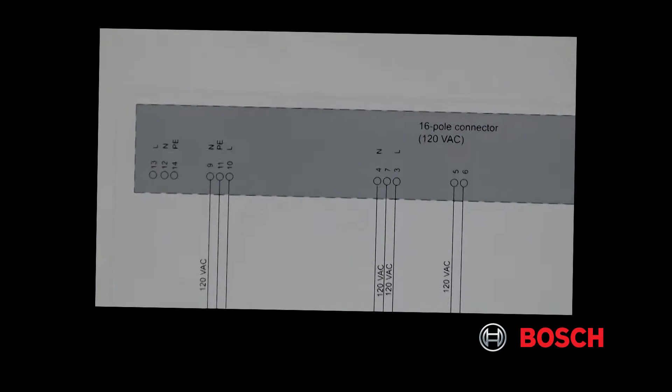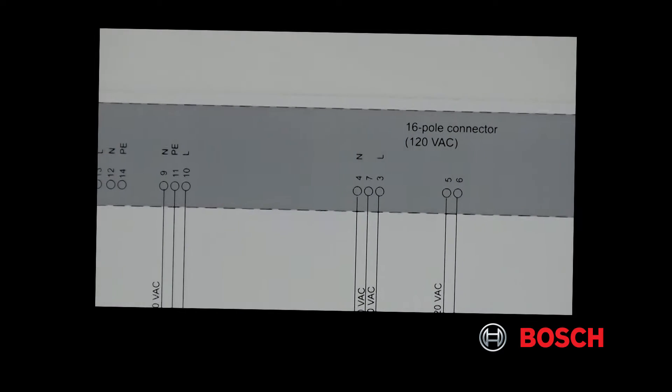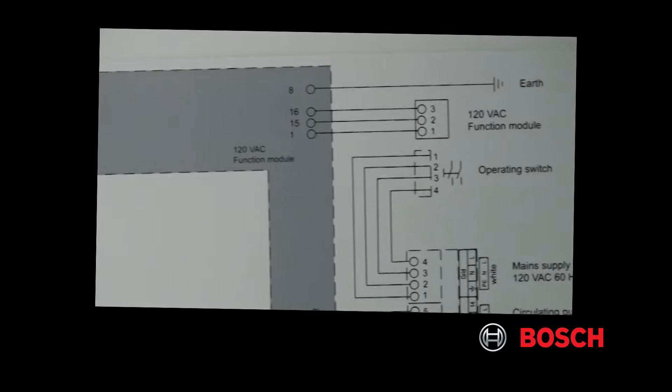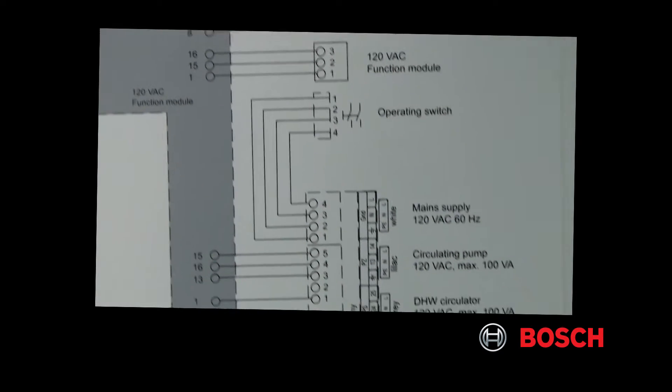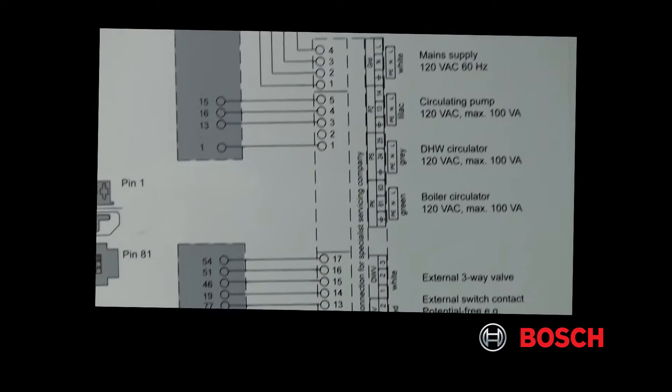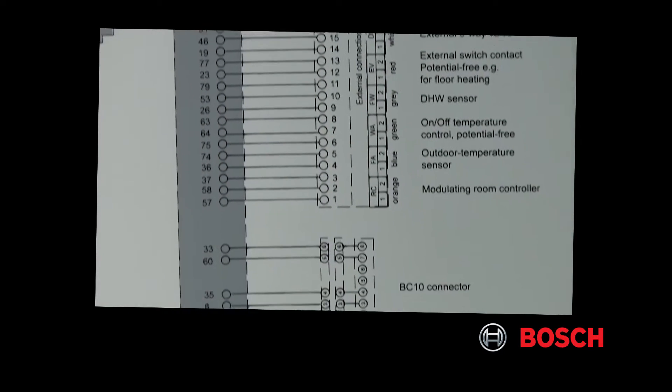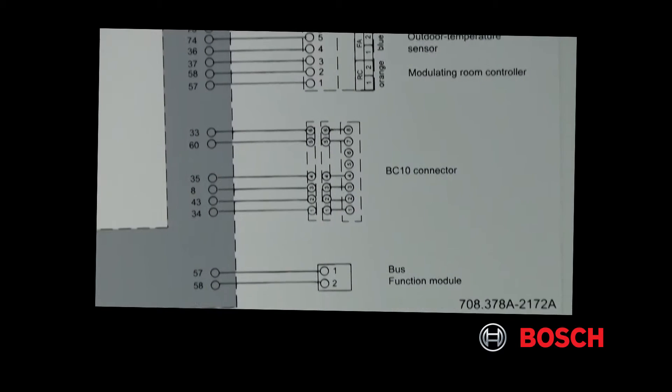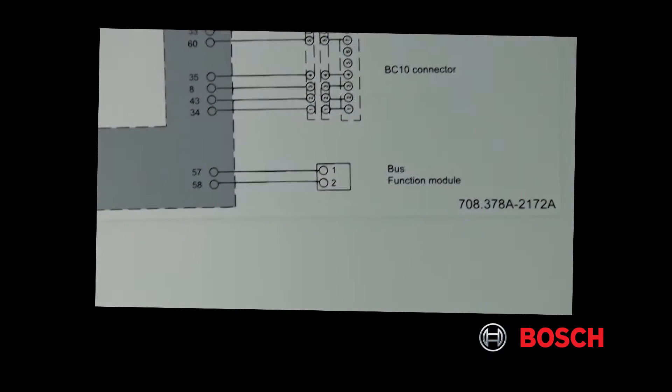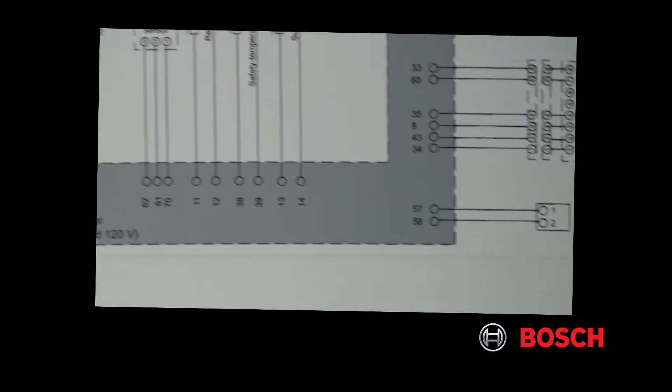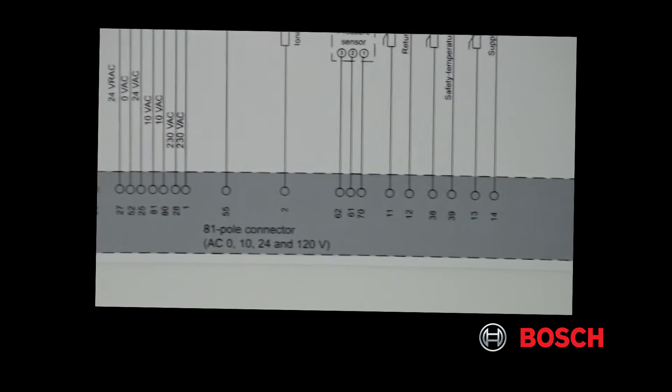The top part of the schematic refers to a 16-pin connector, which in turn is your line voltage to the connections in the boiler. The bottom part of the schematic refers to the 81-pin connector, which is a low voltage connection for your sensors and other items.